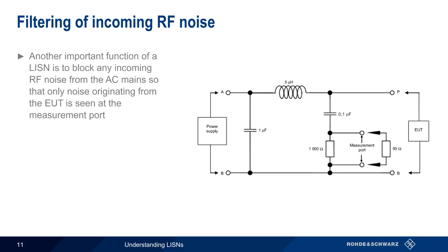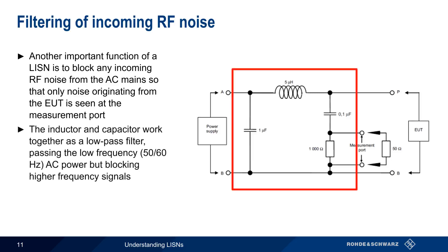Another primary function of a LISN is blocking any RF noise from entering over the AC mains network. This ensures that any noise seen at the measurement port is coming from the EUT and is not being conducted in on the EUT's power cord. The inductor and capacitors in the LISN work together as a low-pass filter, passing the low-frequency AC power but blocking any higher frequency signals.